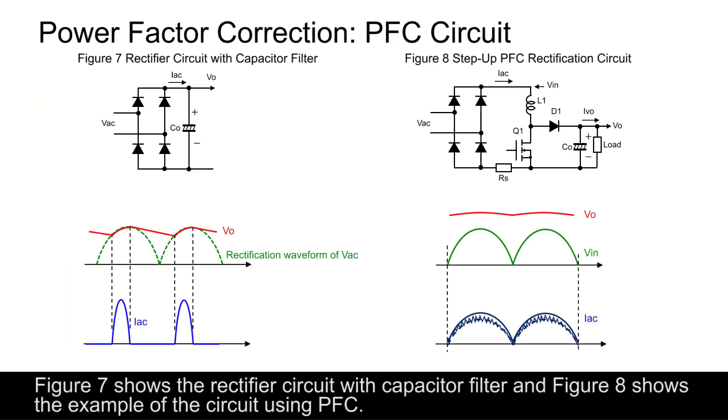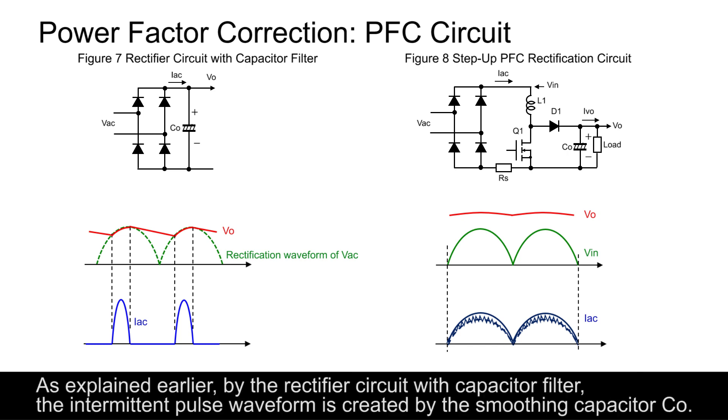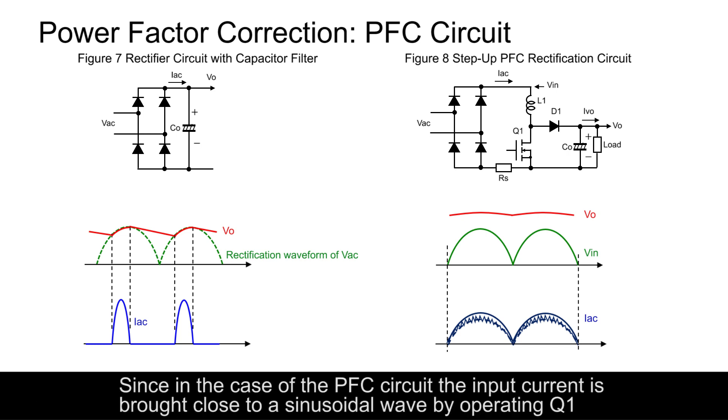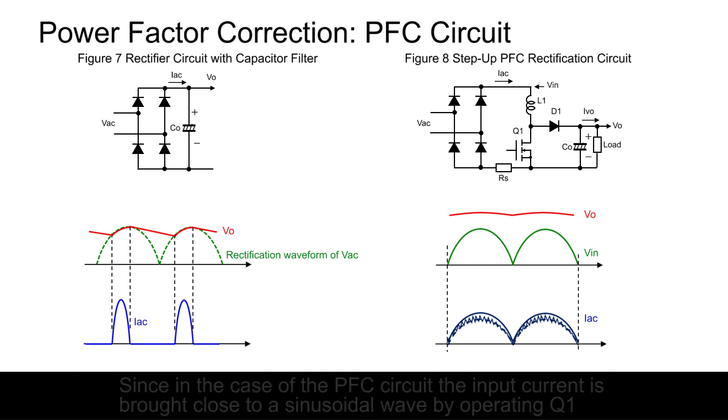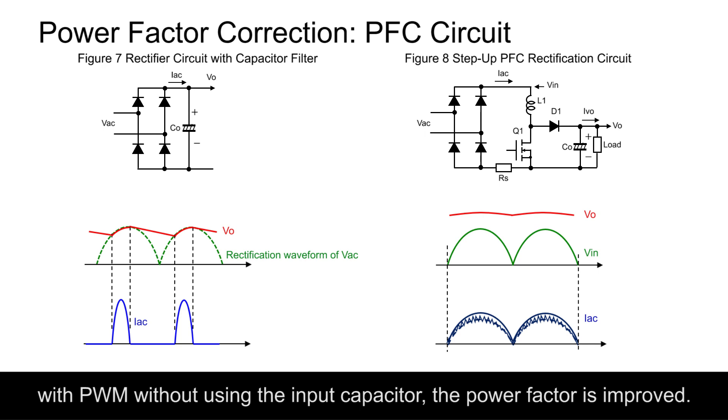Figure 7 shows the rectifier circuit with capacitor filter and Figure 8 shows the example of the circuit using PFC. As explained earlier, by the rectifier circuit with capacitor filter, the intermittent pulse waveform is created by the smoothing capacitor CO. Since in the case of the PFC circuit, the input current is brought close to a sinusoidal wave by operating Q1 with PWM without using the input capacitor, the power factor is improved.